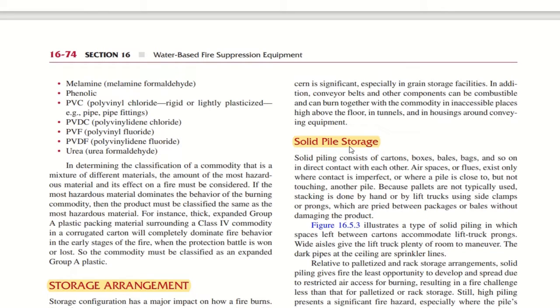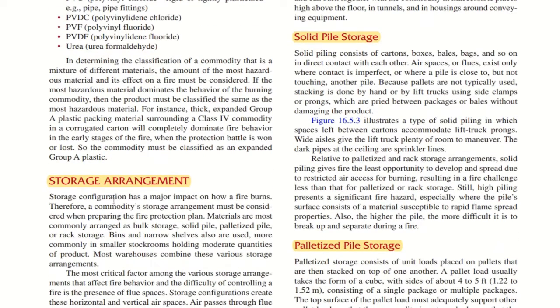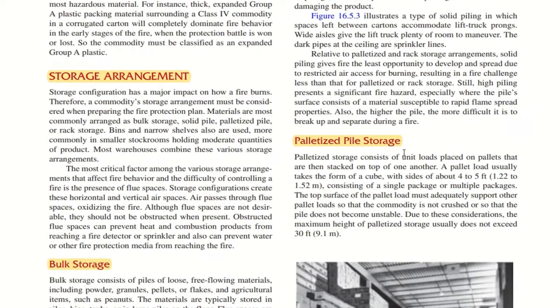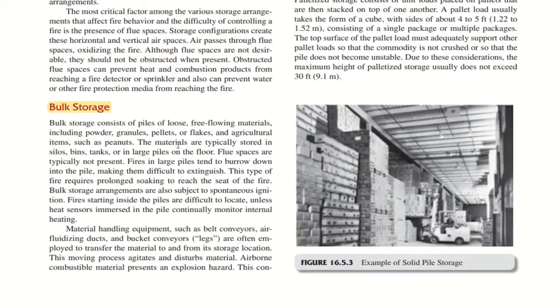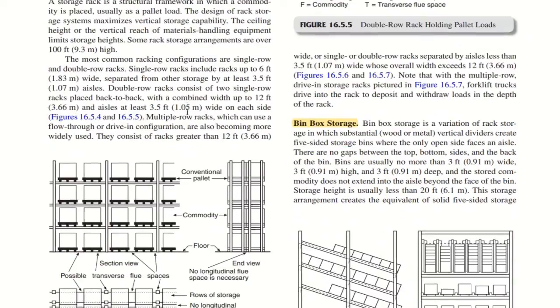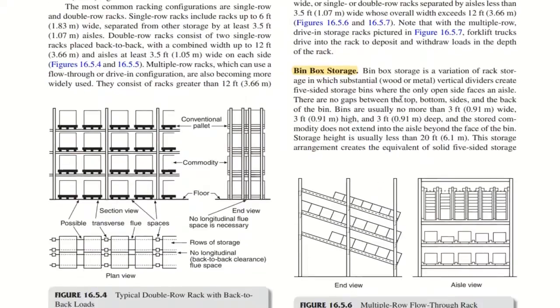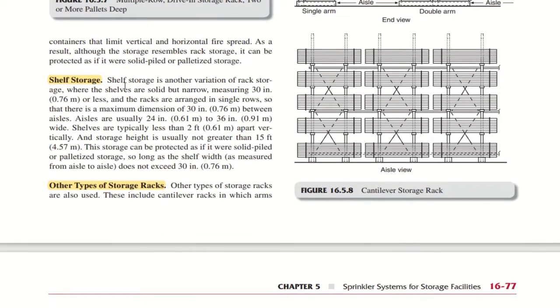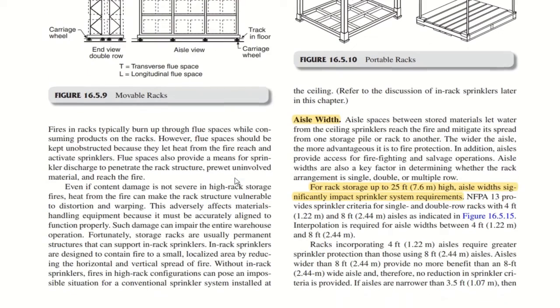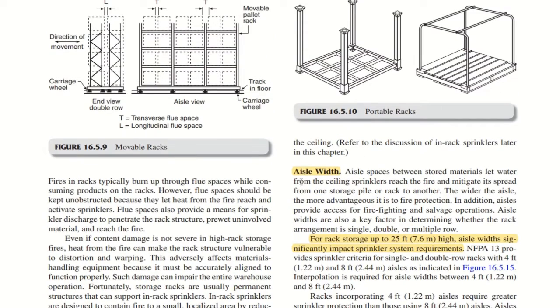So basically for storage applications you need to think that it is referring to the commodity classifications such as class A, class B, class C, or group A, group B, group C, and class 1, class 2, class 3, class 4 commodity classes. And the storage arrangement also is available here, like solid pile storage, palletized pile storage, how we are storing the material. So bulk storage, everything is mentioned here. Rack storage, and you have bin box storage. All these details can be found here. Shelf storage, other types of storage racks. Here there are the widths they mentioned.